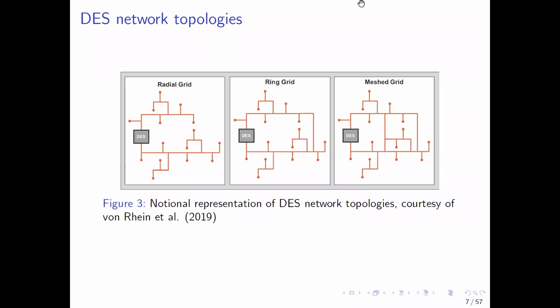At the far right is a meshed grid, in which there exist several potential connection paths from a central plant to each load. This connection configuration would not typically be considered for earlier generations of district thermal energy systems, but is increasingly relevant in light of 5G DHC systems due to the ability of connected loads to offset each other's heating and cooling requirements. This type of network configuration is motivated because each connected load can also be viewed as a source of heating or heat rejection to other loads in the network.